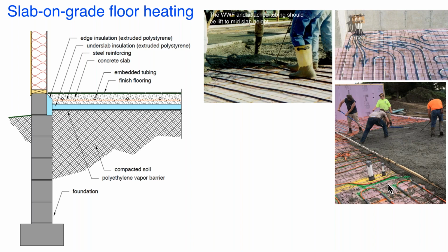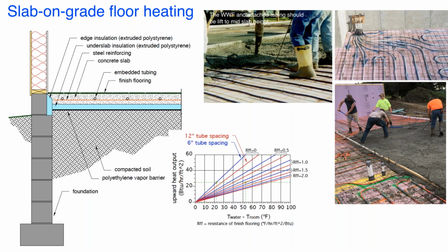If you're new to radiant panel heating, I don't want to spend a lot of time on the details, but for example, there are references where you can look at, if I put the tubing 12 inches on center and I have a finished floor resistance of 1, how much heat output will I get depending on the difference between the average water temperature in the circuit and the room air. So this is a graph. I use this graph a lot. It allows you to get a quick estimate of output in BTUs per hour per square foot versus what I call the driving delta T. And the driving delta T is just the difference between the average water temperature in the circuit and the room air temperature. The higher that is, the higher the heat transfer rate.